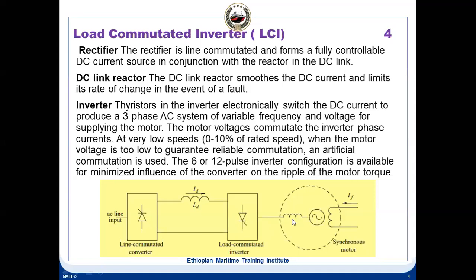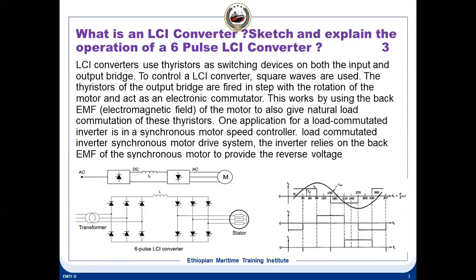At low speeds, when the motor voltage is too low to guarantee reliable commutation, artificial commutation is used. At lower speed, this back EMF will not be high enough to cut off the thyristor, so there is an additional circuit for that. This is a synchronous motor. This type of converter, load commutated converters, are used only with the synchronous motor. So this diagram is good enough, and this explanation is also good enough. So you can draw this 6-pulse load commutated inverter, and this is the explanation of how it is working.